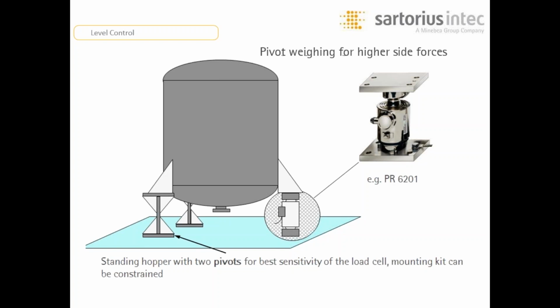You don't always have to have the pivots on the back 2 legs. If you have just a 3-leg system, the 2 in the back can remain bolted securely to the floor, and the 3rd leg can be raised and set on top of a very low-profile sensor made by Sartorius Intec in order to provide them with an accurate representation of the level.